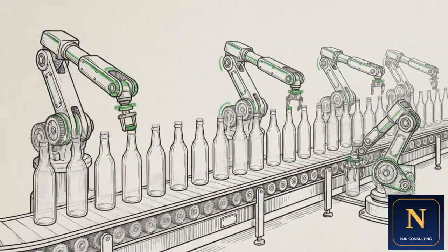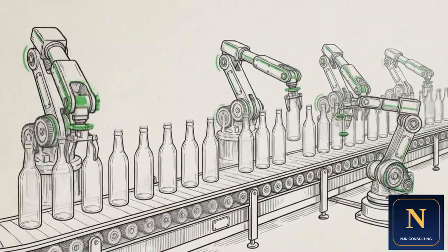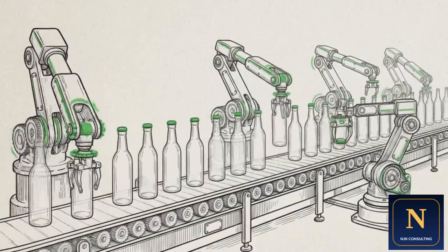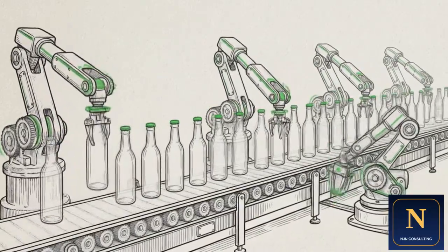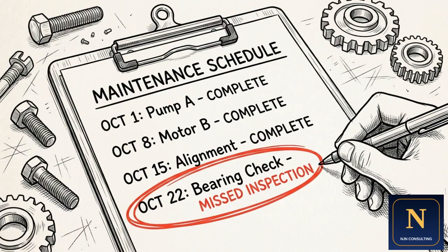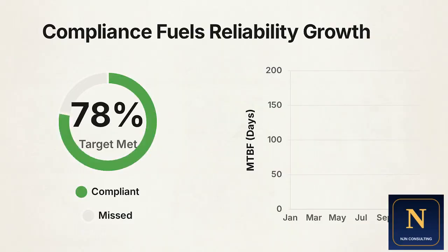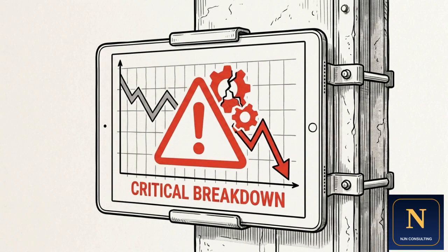By following this methodology, you elevate your facility. You transition out of reactive firefighting and secure a documented, risk-prioritized, and system-integrated maintenance engine. However, maintenance tactics require ongoing review. You must track lagging indicators, paying close attention to your PM compliance rates and your mean time between failures. If an asset continues to fail despite executing the scheduled plan, that data serves as your trigger. You pull the failure mode back into review, analyze the gap, and adjust the tactic.